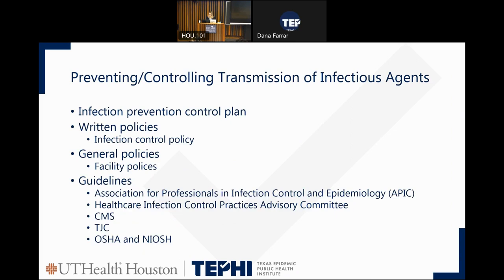Monitoring these components is critical. Monitoring programs must be conducted to ensure proper cleaning, disinfection, and sterilization practices are present. Many times, sterilization systems have built-in quality assurance measures, such as mechanical indicators, recording charts of load times and temperatures, along with monitoring the pressure gauges within the cycle load.